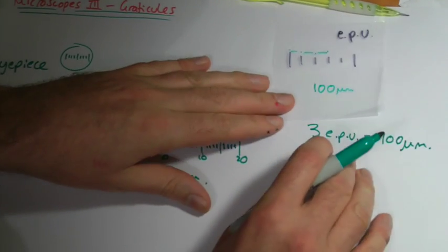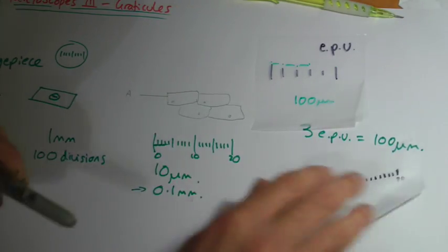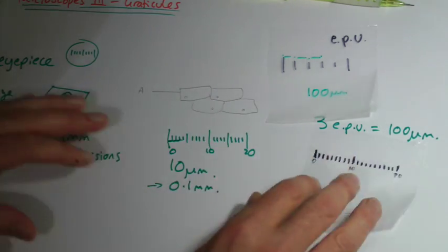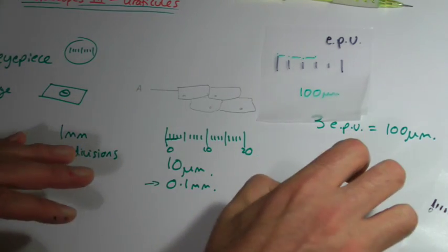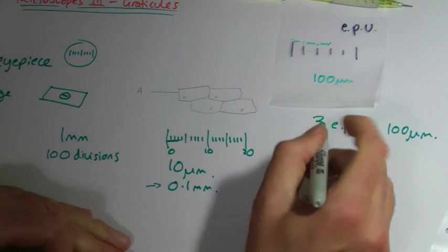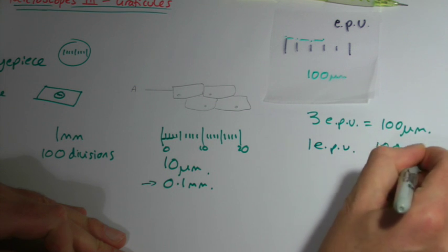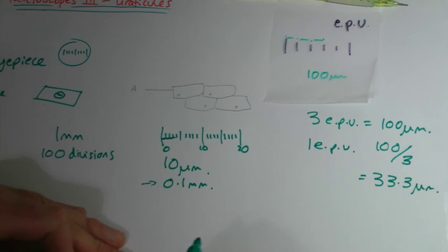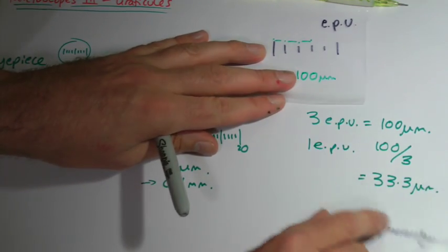That's on that particular magnification. Every time you change the objective lens, because the lenses have slight differences in them, you would have to recalibrate this. You might think it should come out exactly the same — no, you've got to redo it every time. So, if three eyepiece units are a hundred microns, then one eyepiece unit is going to be a hundred divided by three microns, which is 33.3 microns. So I took the number of microns and divided it by the eyepiece units.